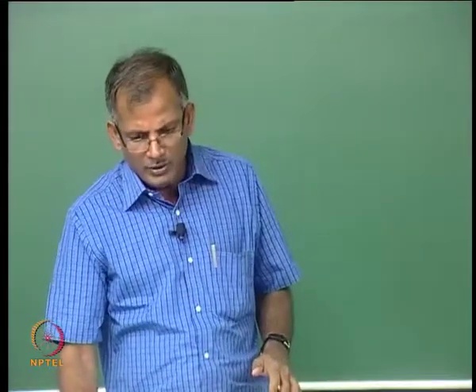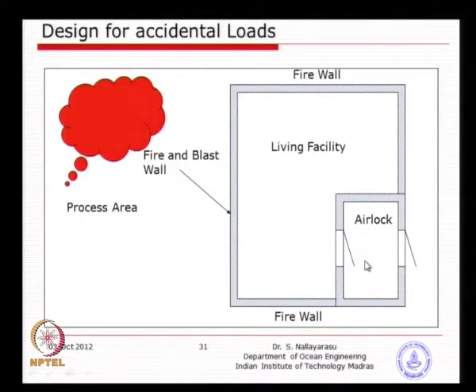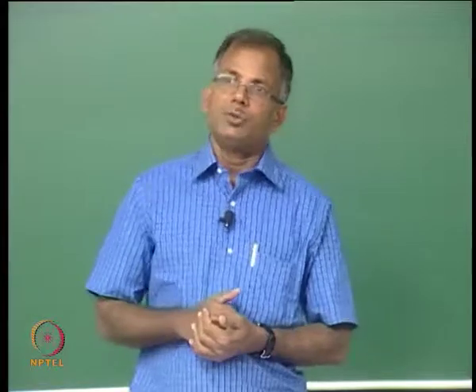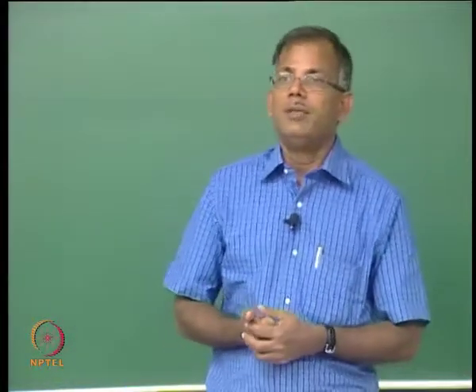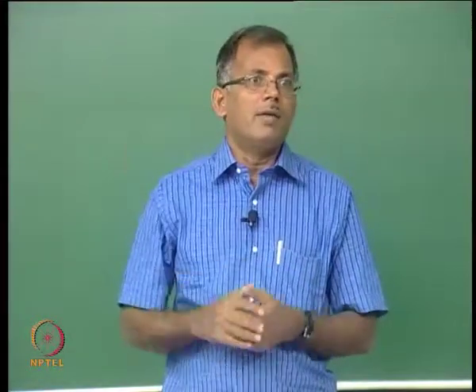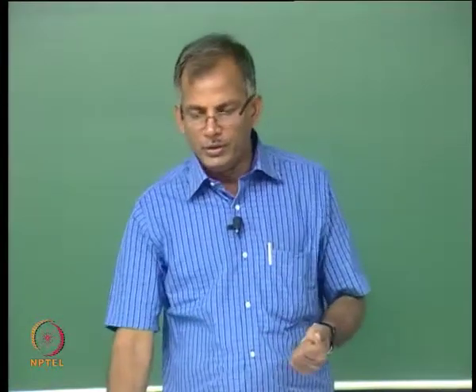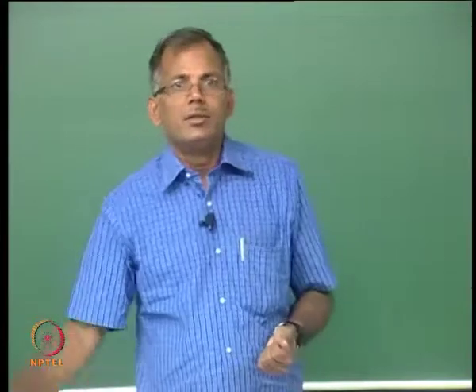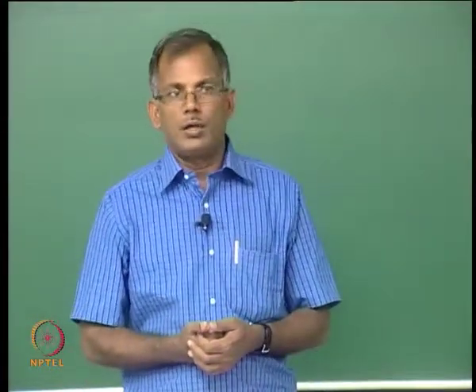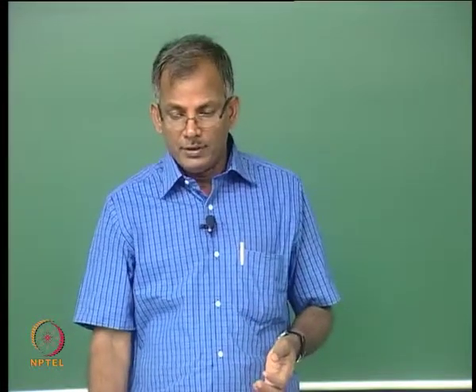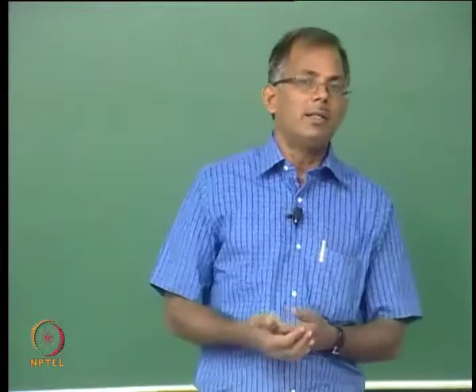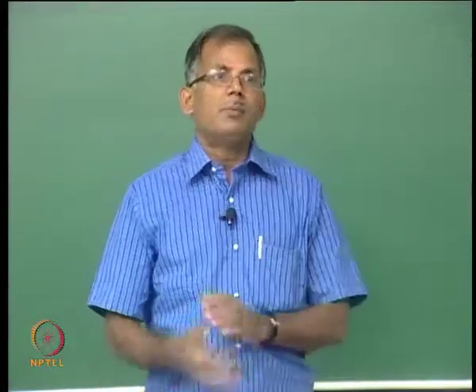Another requirement in most offshore facilities is the airlock, which is essential to reduce the risk of smoke entering the facility. If you have a single door, smoke ingress will cause tremendous problems to the living facility — it will get into circulation and affect almost all people. You need to create a barrier with an exhaust so that if smoke or gas enters the building, the airlock chamber evacuates it, not allowing it into the main building.